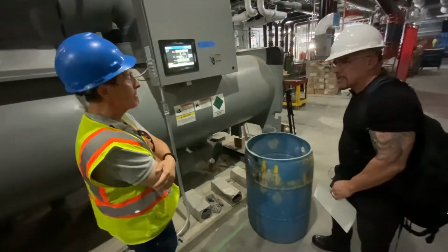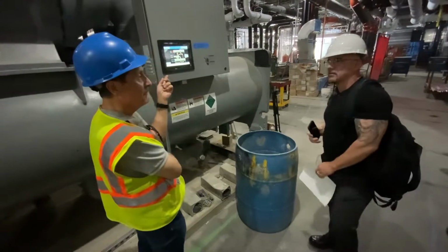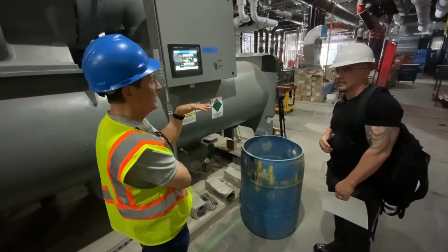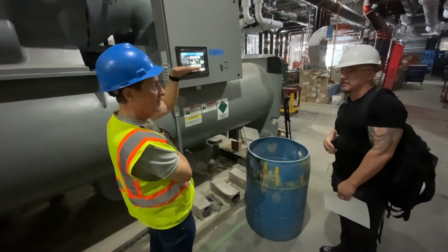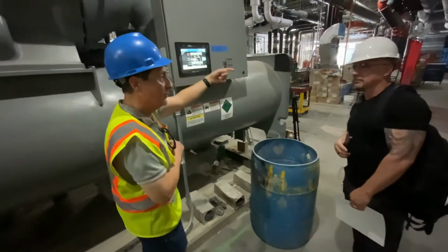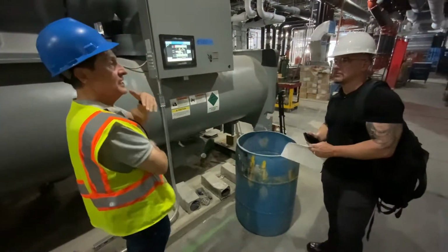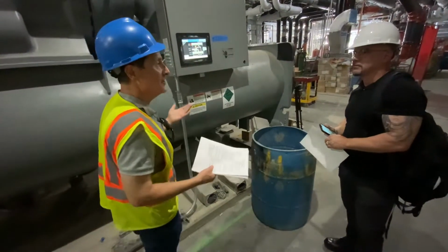What's your recommendation, like 78? Minimum tower temperature about 75. If you got a good load, I use 75 as an all-encompassing because a low load wants, believe it or not, higher temperature to move that refrigerant through the system. But if you're at high load, this machine could run fine with down to 55 degree water. So rather than give you all different numbers, if you stay at 75, that works at all loads.